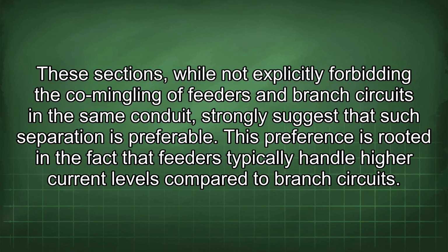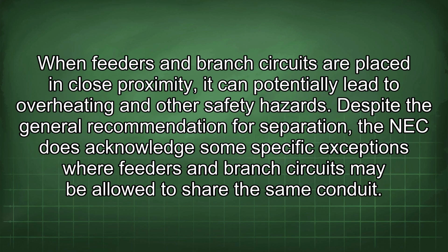These sections, while not explicitly forbidding the commingling of feeders and branch circuits in the same conduit, strongly suggest that such separation is preferable. This preference is rooted in the fact that feeders typically handle higher current levels compared to branch circuits. When feeders and branch circuits are placed in close proximity, it can potentially lead to overheating and other safety hazards. Despite the general recommendation for separation, the NEC does acknowledge some specific exceptions where feeders and branch circuits may be allowed to share the same conduit.